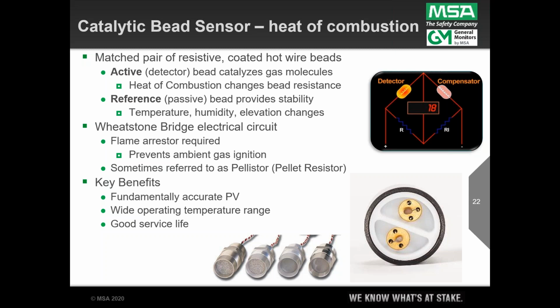And this is passive. It's coated with glass. But these beads have the same electrical resistance in clean air, and so they're a balanced circuit in clean air. But when vapors permeate through the flame arrestor around that Wheatstone bridge circuit, the molecules of gas contact the active bead, which creates heat, which changes the resistance of the circuit proportional to the concentration of vapor in the measurement chamber. And that measurement chamber is shown in the lower right-hand corner.